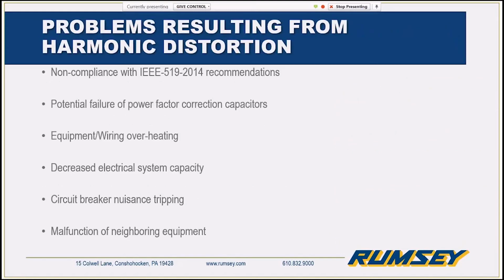So then we're going to spend some time now talking about some of the problems that result from harmonic distortion, then get into active harmonic filters specifically and how they compare to other mitigation techniques that are out there. Because as Sean said, we are a tool in the toolbox. You'll find that as we talk, the quantity of drives, the total amount of horsepower, the size, how much room you have physically will help determine which option's best for you. So we'll start off with IEEE 519, talking a little bit about all the other main problems that you'll see with equipment wiring overheating, malfunctioning in equipment, and power factor correction capacitor failures.